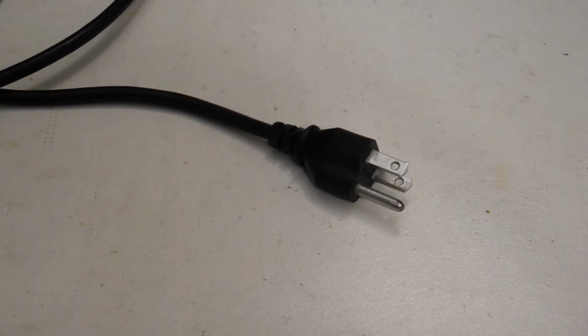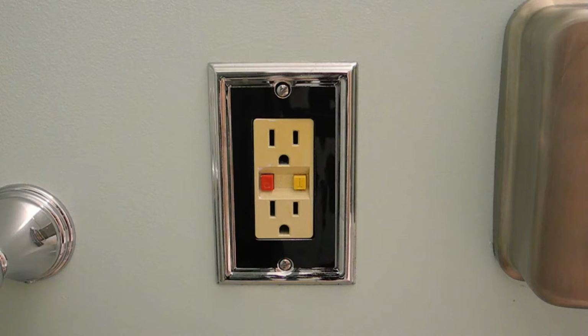A device in a metal case should be connected to ground. Some circuits may have a ground fault interrupter which detects a small current flow, 4 to 5 milliamps, from the line or neutral to ground and shuts off the power. This is designed to prevent electrocution where a person touches a live wire and is grounded, and is often legally required in potentially wet areas like bathrooms or outside outlets.